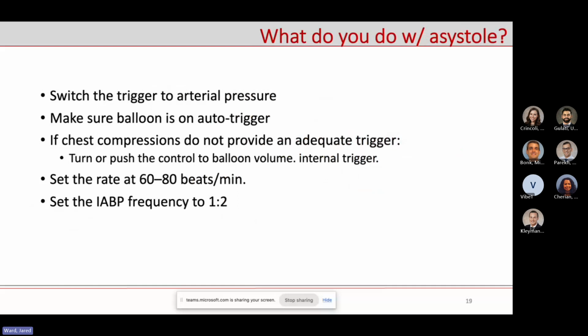But what do you do when the patient, if they were to go into asystole, and they had a balloon pump in, right? So you can switch the trigger over to the arterial pressure, and that should cause the balloon to auto trigger every time it sees some sort of arterial waveform with chest compressions. But you can also switch off of that to control the balloon volume with an internal trigger. Basically, with that, you can just set the rate to 60, 80, and you would just set it to augment 1 to 2. These in general are really a problem because the balloon isn't necessarily, or you could just put the balloon on standby and just do regular chest compressions and hope that you revive the patient.